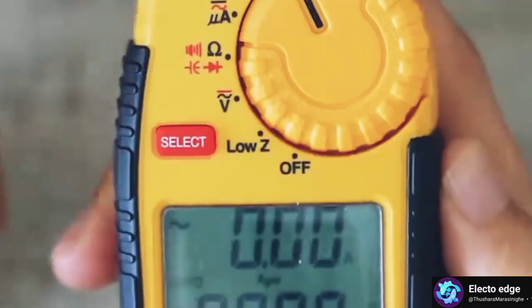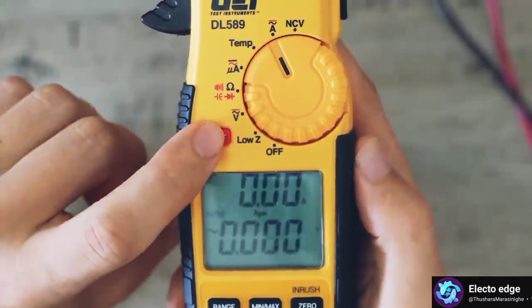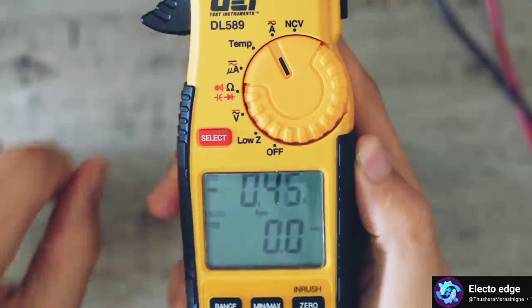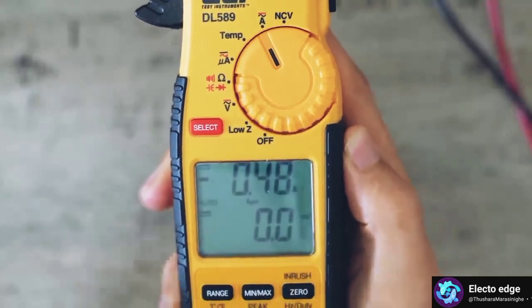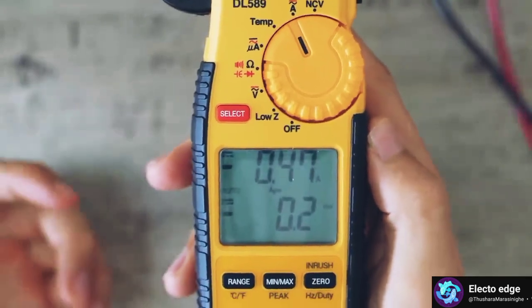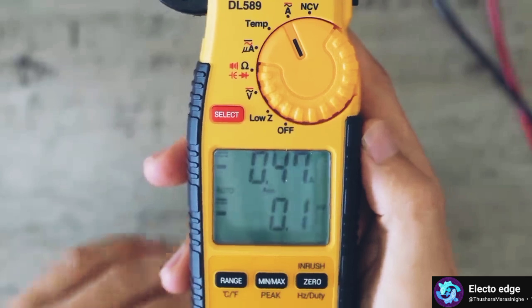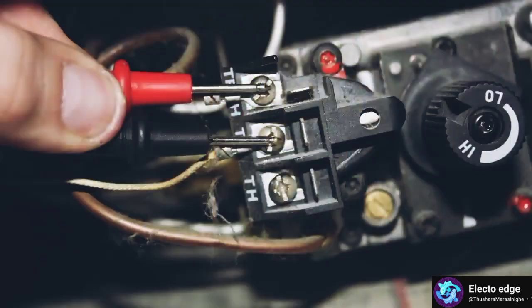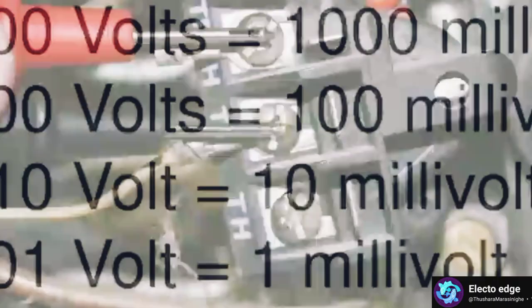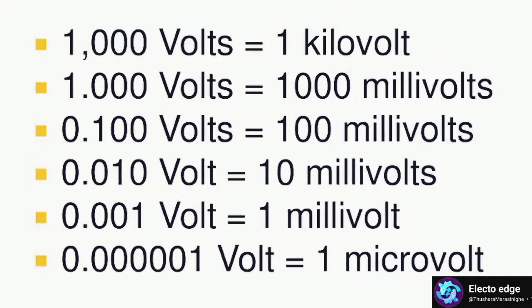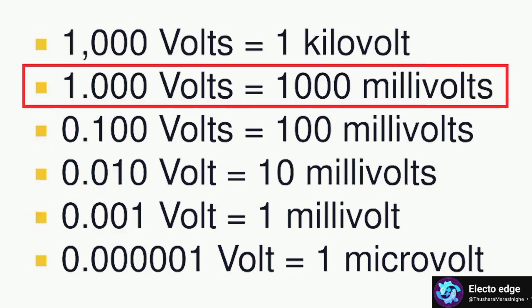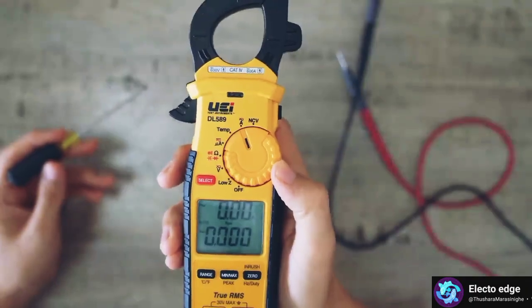You can also check millivolts with this meter by pressing the select button, and we see a little M up here. So if you're using your meter to check something that has really tiny voltages, like fractions of a volt, you can use this setting to accurately measure those voltages. Keep in mind that voltage and millivoltage are very different. A millivolt is only 1/1000th of a volt. And then we also have this setting.